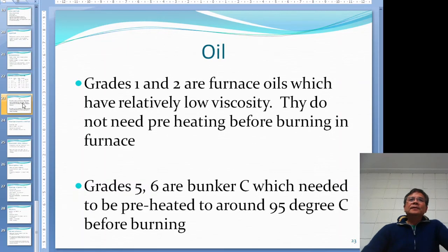Heavy oil. Now, grade 1 and grade 2 furnace oil have really low viscosity, so they do not need preheating before burning in the furnace. You just pump it in and spray it, and then it will burn. But the bunker C, you refer to grade number 5 and 6, those are the heavier oil.